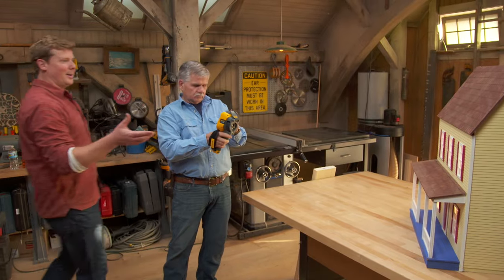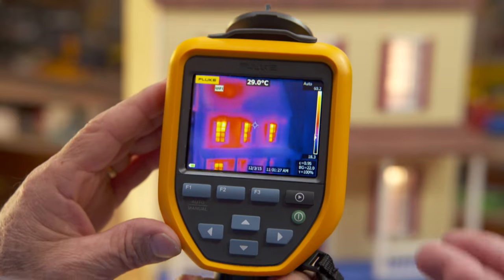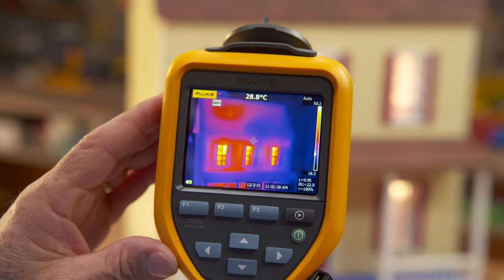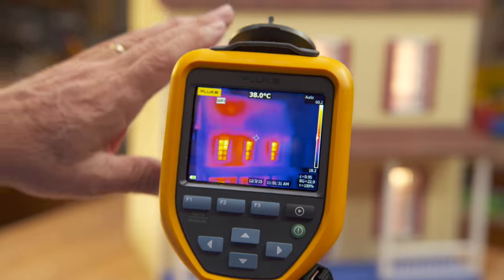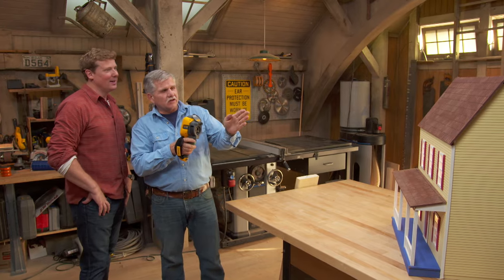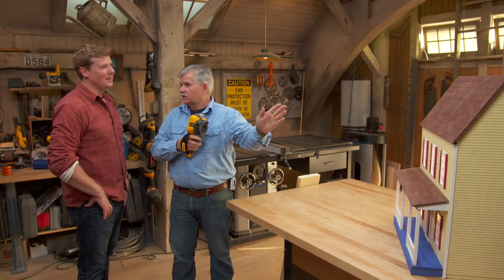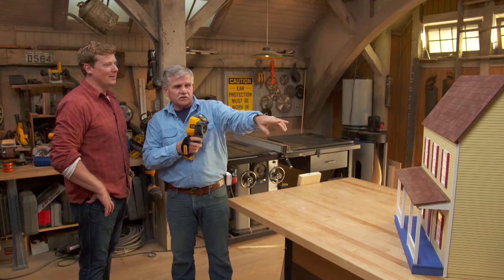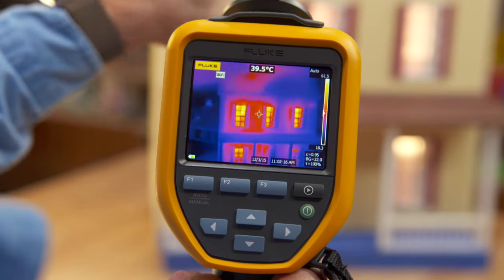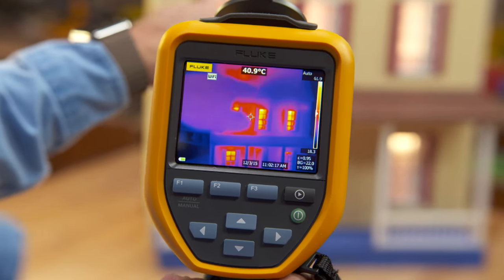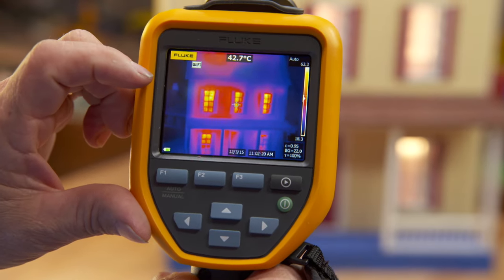Tommy, when you said we were going to use a dollhouse to talk about insulation, you didn't tell me you had an infrared camera. This is really cool. What are you looking at? What I've done in a dollhouse is I've insulated half of the dollhouse and put some heat lamps inside. By looking through the infrared camera, you can really see the heat loss and where it is.